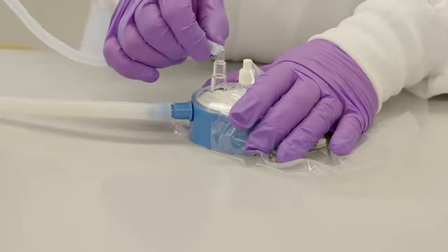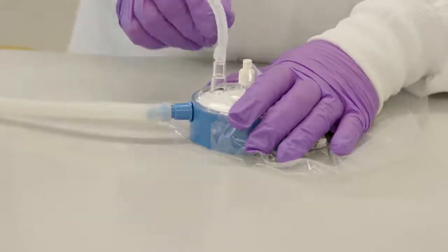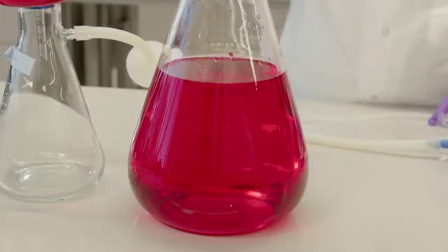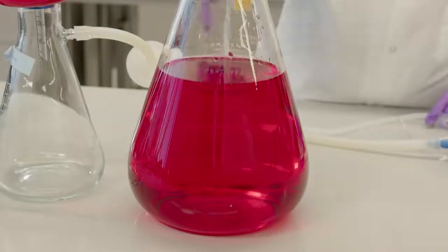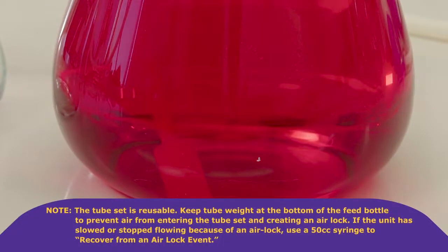Connect the feed tube to the barbed fitting marked inlet on the clear dome top of the device. Place the other end of the tube into the solution you want to filter with the tube weight at the bottom of the feeder container. Note, the tube set is reusable. Keep the tube weight at the bottom of the feed bottle to prevent air from entering the tube set and creating an airlock.